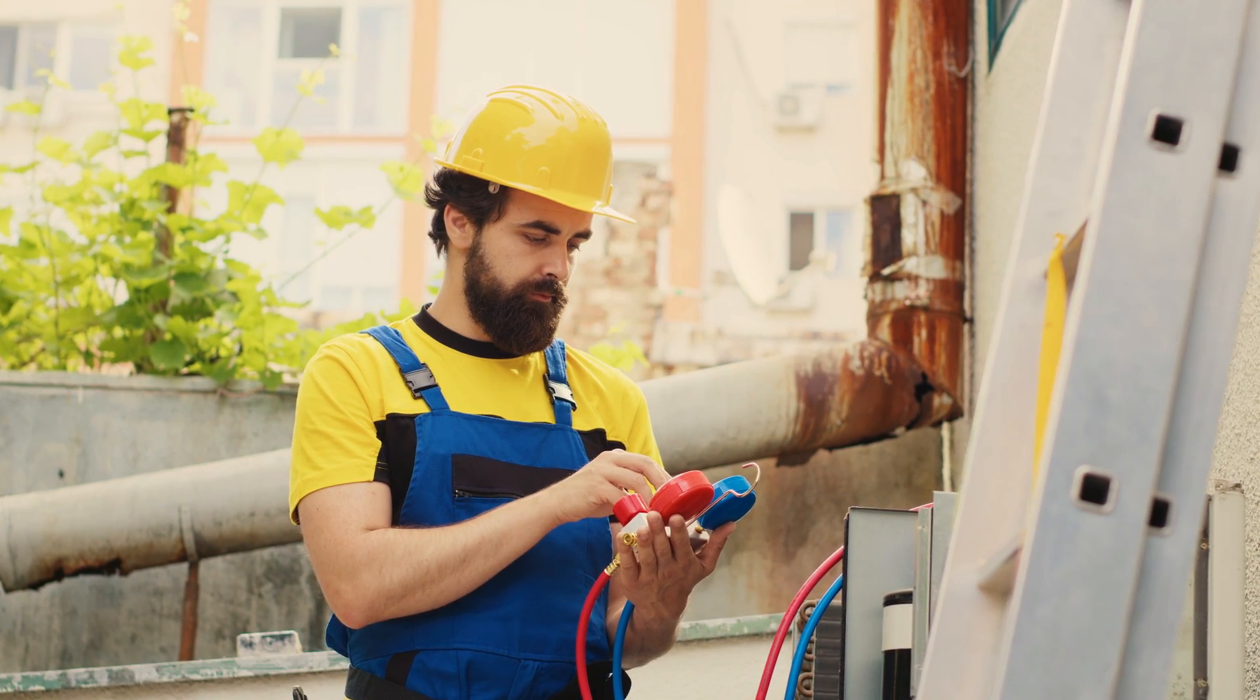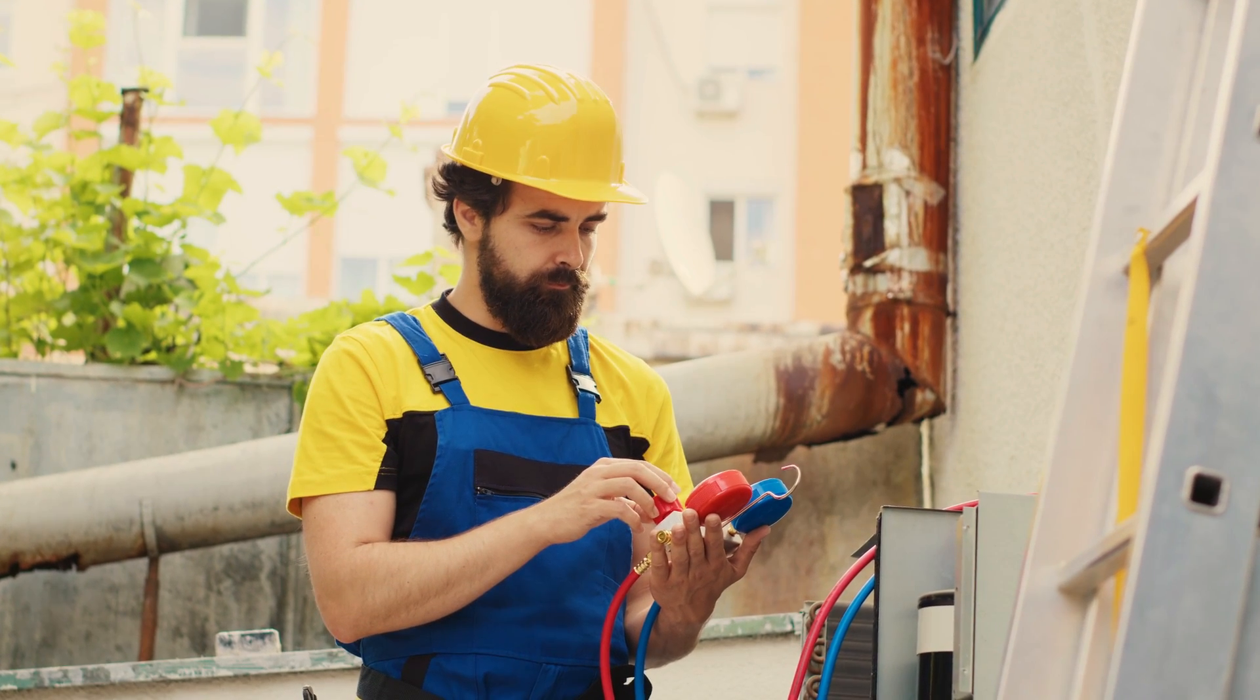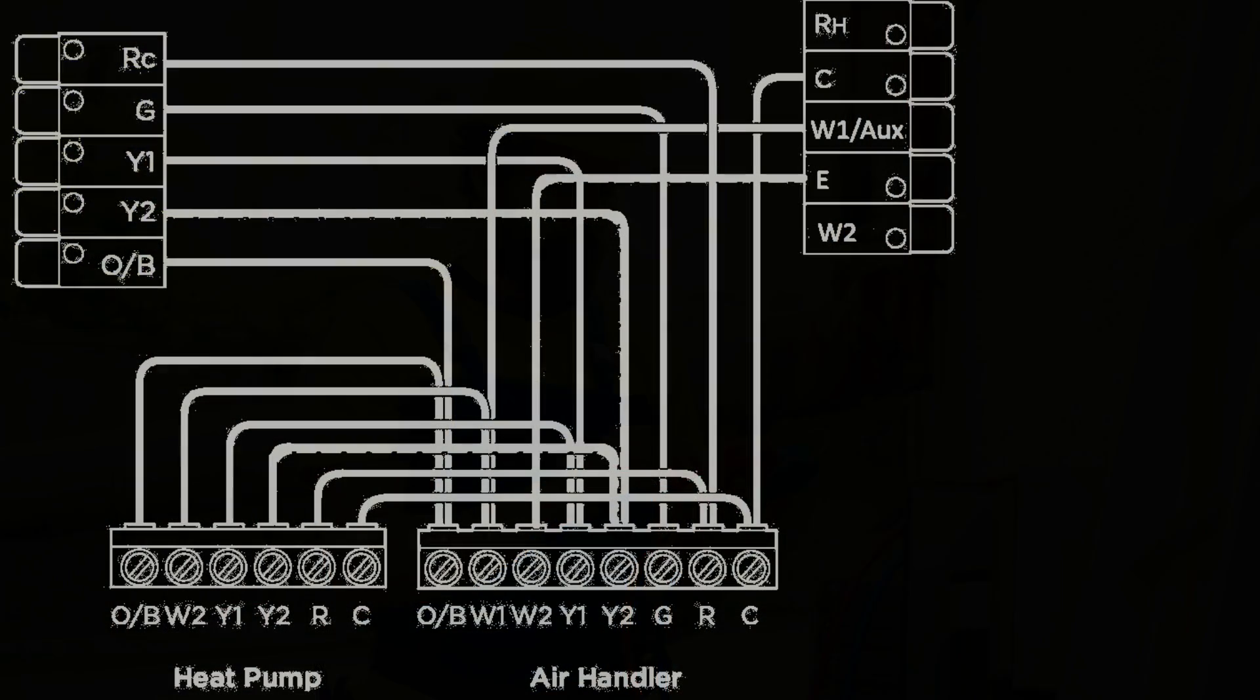Brand new two-stage heat pump systems have to be running in second stage in order to properly balance the refrigerant charge in the system. So obviously knowing how and when second stage is activated is pretty important in that process.